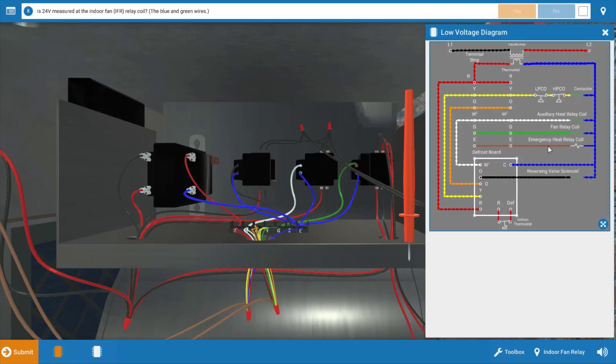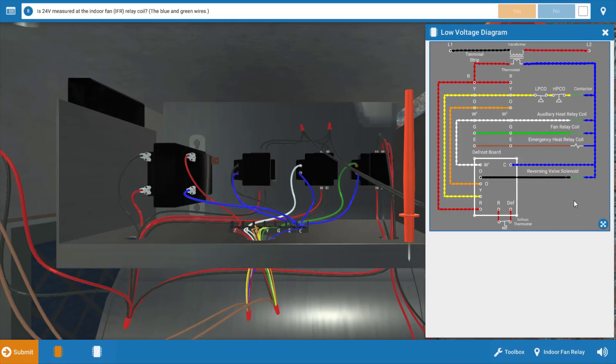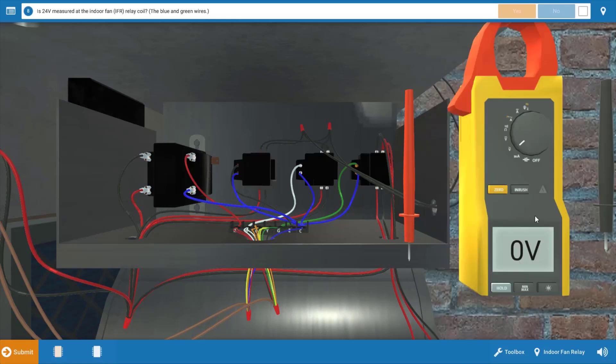Now I'm going to take out the low voltage diagram. If we look here, we can see that the thermostat also sends power to the fan relay coil. So we have four possibilities here: the indoor fan motor, the capacitor, the fan relay, or possibly the fan switch within the thermostat. And again, we're going to investigate each of these.